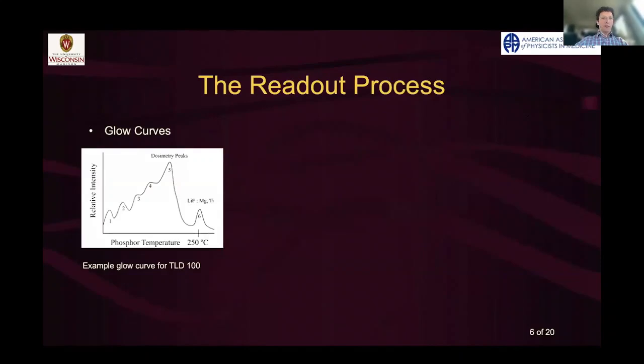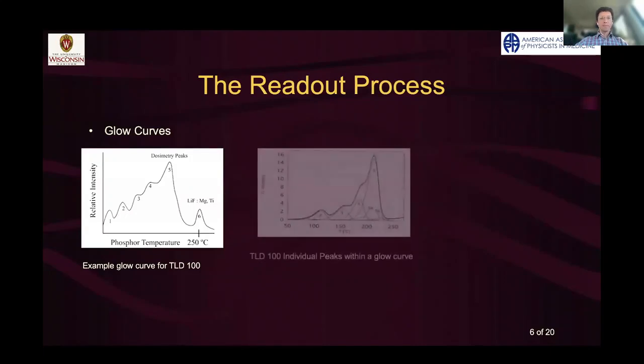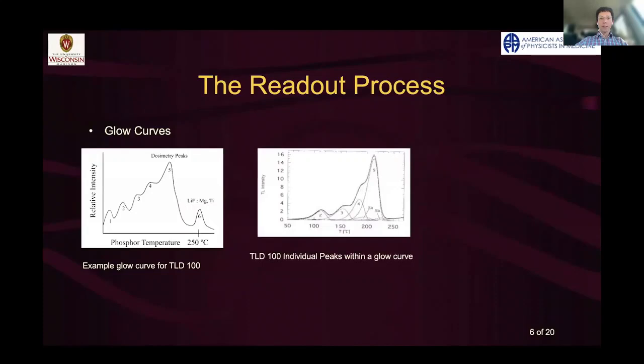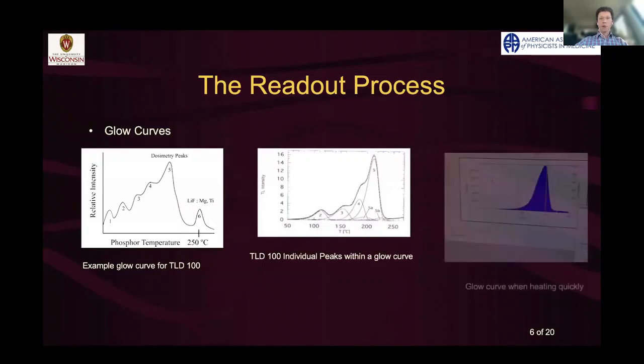The readout process itself involves a glow curve. This is an example of a glow curve for a TLD 100 material. And here you can see the various peaks. As the temperature increases and the TLD is heated up, there are different trap levels that are released. So you see these different peak intensities. And those, in theory, can be deconvolved to see the individual impurity peaks within that glow curve.